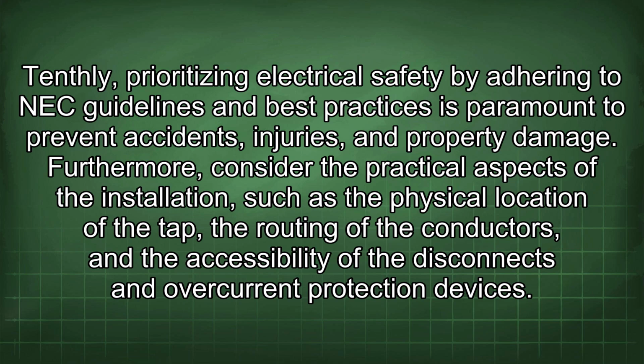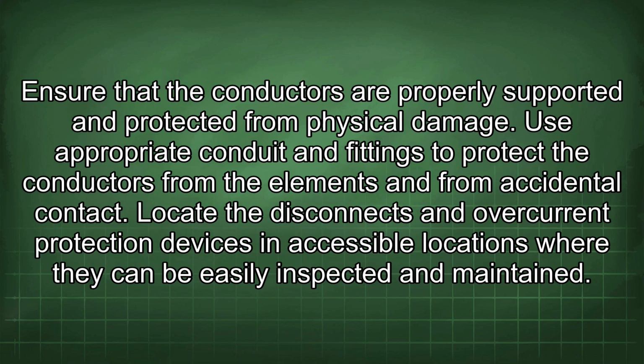and property damage. Furthermore, consider the practical aspects of the installation, such as the physical location of the tap, the routing of the conductors, and the accessibility of the disconnects and overcurrent protection devices. Ensure that the conductors are properly supported and protected from physical damage. Use appropriate conduit and fittings to protect the conductors from the elements and from accidental contact. Locate the disconnects and overcurrent protection devices in accessible locations where they can be easily inspected and maintained.